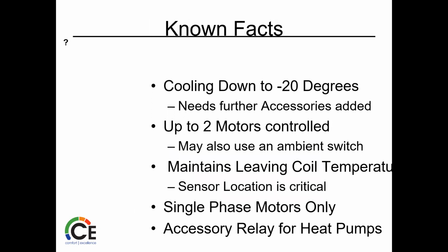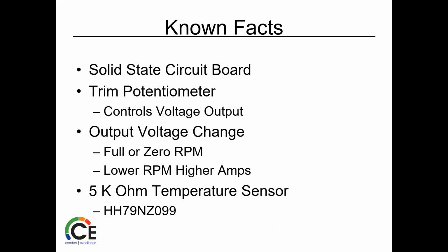Down to 20 degrees again, does everything, further accessories, right? So we're talking wind baffles or whatever. You can do 2 motors with this one. So depending on the size of the unit, you can shut 2 down if you want to. That's weird. That got pushed over to the side. I'm sorry. Maintains leaving coil temperature. Sensor location again is critical, just like all the others. Single phase motors, accessory relay for heat pumps. Same as all before. Solid state control board in there. There's a potentiometer in there. Controls voltage output. Output voltage change, full or 0. Lower RPMs, higher amps. 5 K ohm temperature thermistor. So that throws people off sometimes because they're so used to the 10K with the other ones. So same operation, different chart to check it.